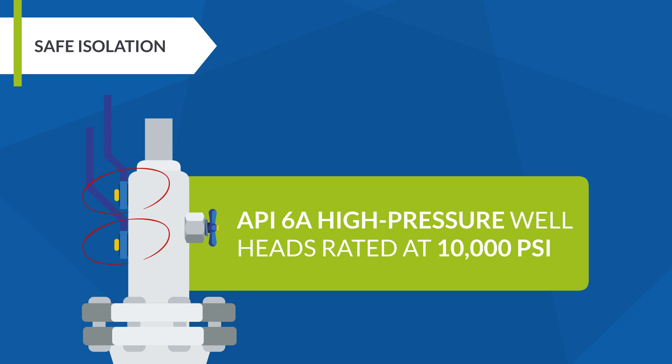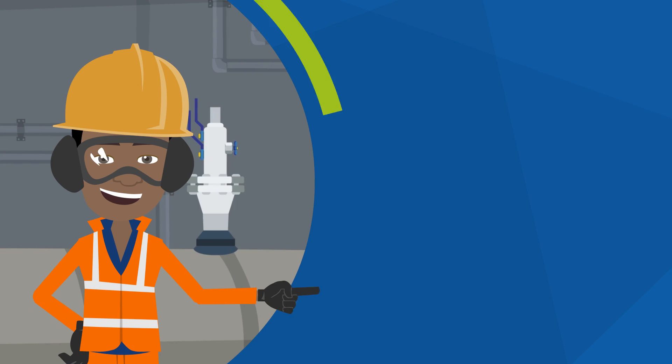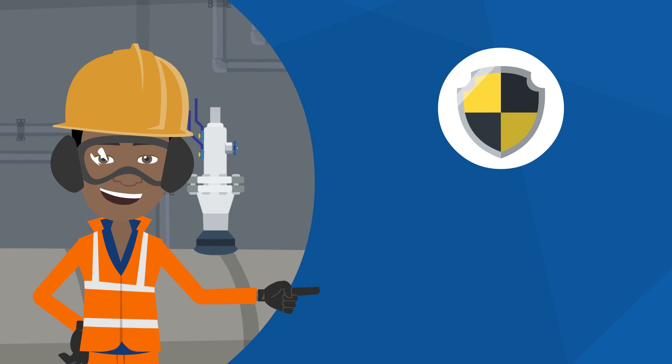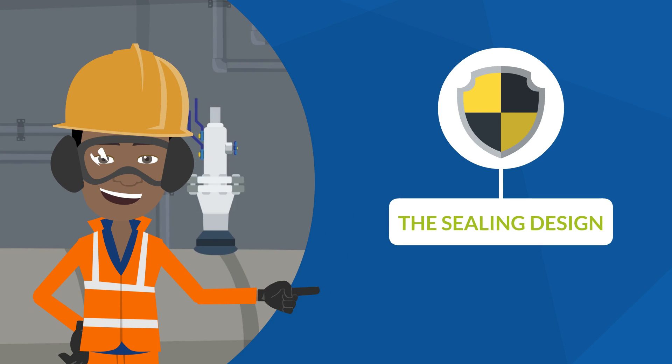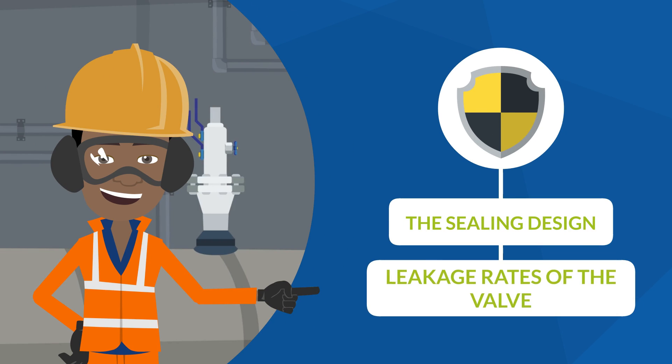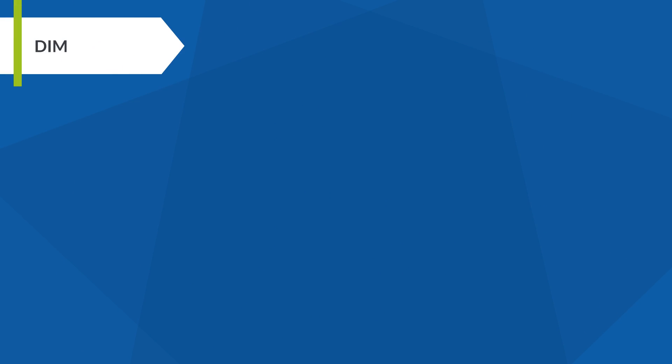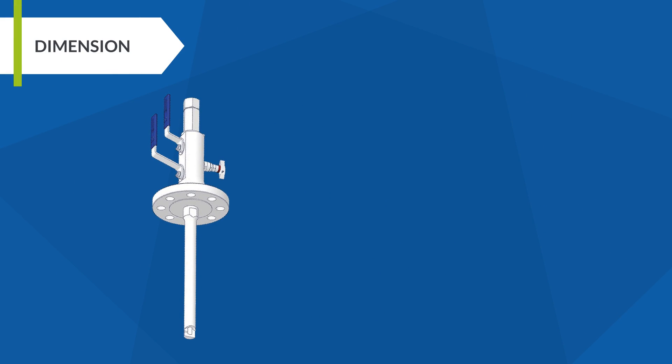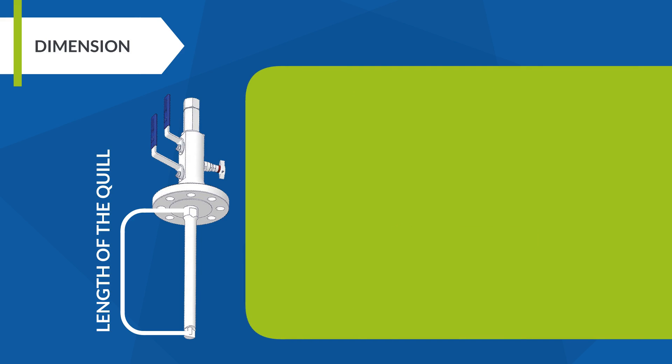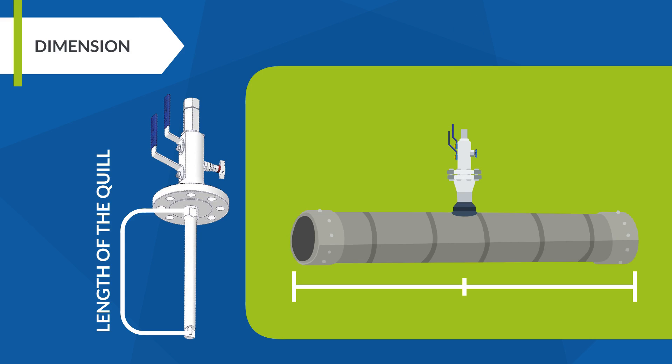Talking about safety, the sealing design and leakage rates of the valve are critical too. Dimension: one of the most important parameters in the wake frequency calculation is the length of the quill. The length is usually customized or as specified. In general, the injected chemical is dispersed well if the nozzles are positioned at the center of the pipeline.